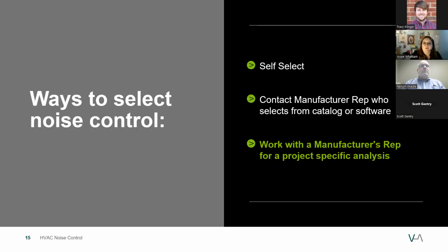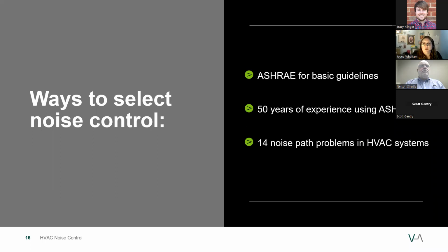So method number 1 to select noise control would be self-selection using a catalog or a software. Method number 2 would be contacting your manufacturer's rep who self-selects from catalog or software. Or method number 3, which is working with a manufacturer's rep who can provide project-specific analyses. I'm going to explain why the first 2 methods are potentially time savers for designers, but highly discouraged. So we're all aware that ASHRAE provides some basic guidelines to follow for applying noise control to HVAC systems. However, many of them are not practical.